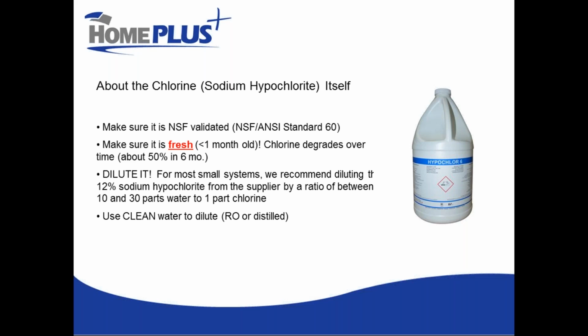So think about this for a second. If I'm injecting a really strong solution, especially during periods of lower flow rates, in order to not over-chlorinate, my chemical feed pump is going to inject, and then it's going to have a big, long pause, because it has to stop injecting, otherwise it's going to over-chlorinate. Eventually, it will inject again. So what I'm going to have running through my line and potentially through my contact system is really strong chlorine, followed by virtually no chlorine, followed by really strong chlorine again. And that's undesirable because it makes it very, very hard for you to get consistent test results. It also interferes with proper disinfection. Mixing helps alleviate that problem.